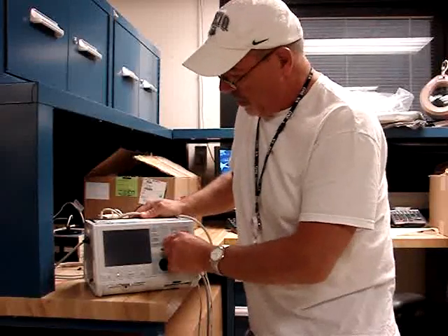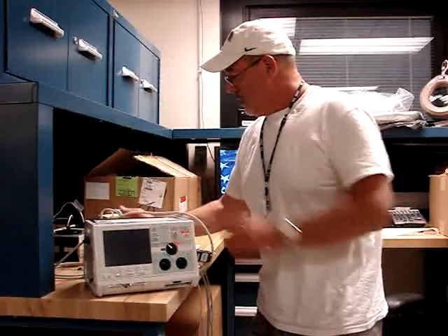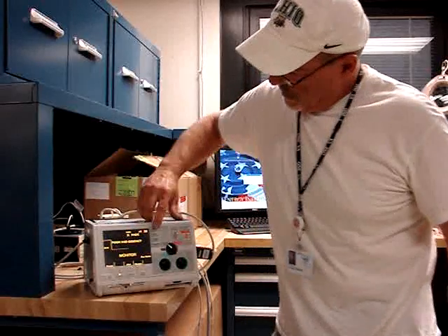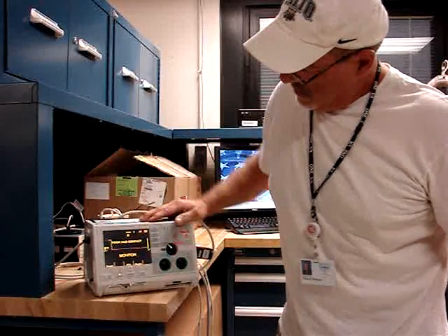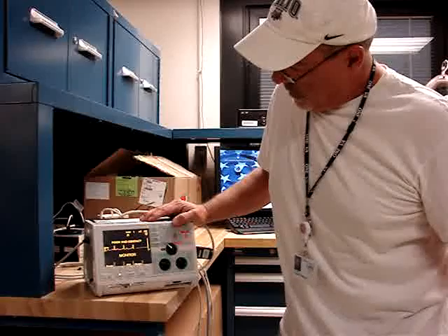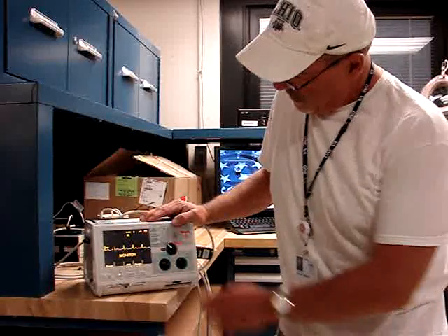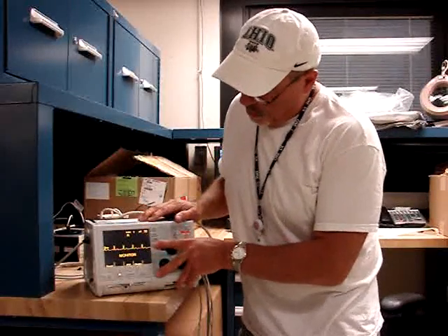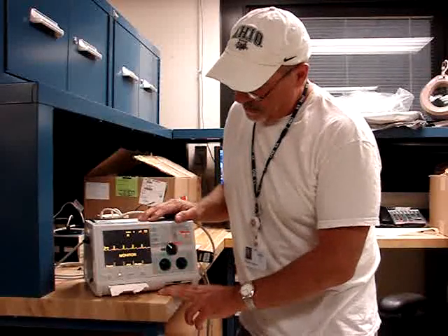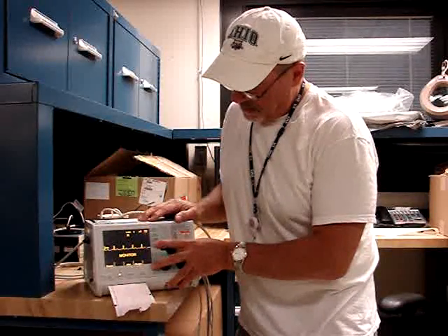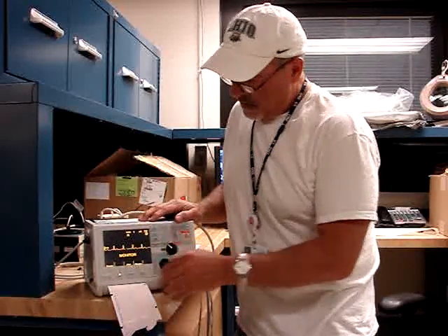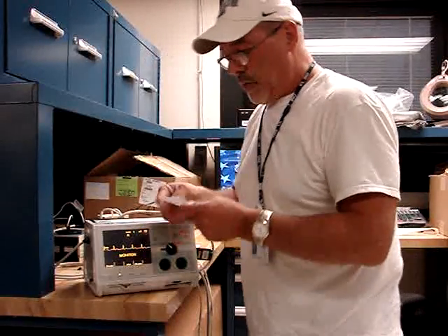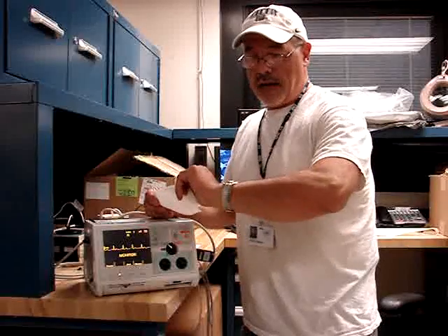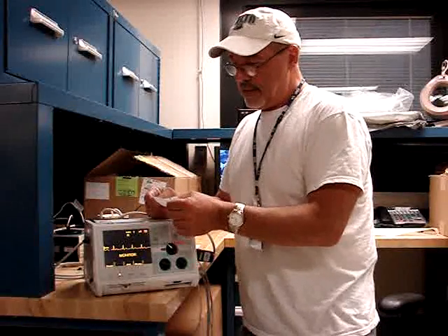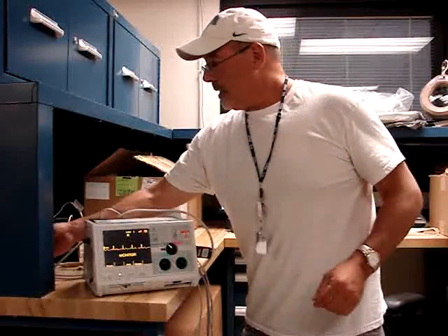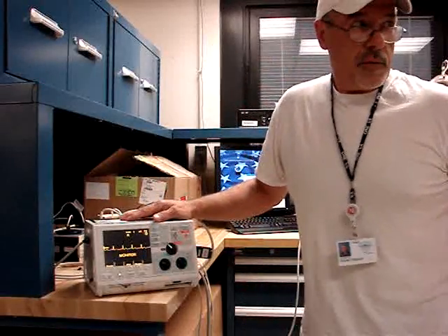And then I'm going to turn the unit on. I've already got it hooked up to the analyzer. We're going to go ahead and get a trace, got a heartbeat coming across from the analyzer. And then we're going to record it. And as we do that, now we're going to go ahead and check our time. Time's good. Date is good. And I believe that takes care of the recorder.